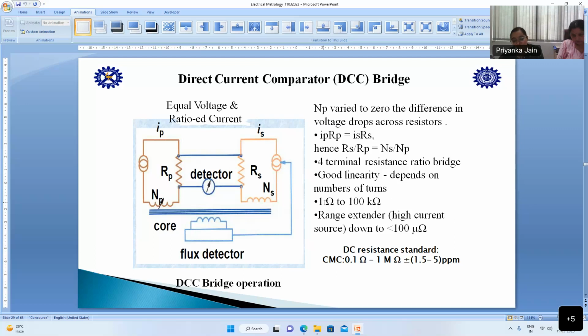In the higher range, that means for mega ohm calibration, it works on voltage balancing. In the normal ohm range, that is 1 ohm to 100 kilo ohm, the DCC bridge will operate at we have CMCs using the DCC bridge. The particular one is 0.1 ohm to 1 mega ohm. This is normally used for all the industries. So the uncertainty is 1.5 ppm to 5 ppm.